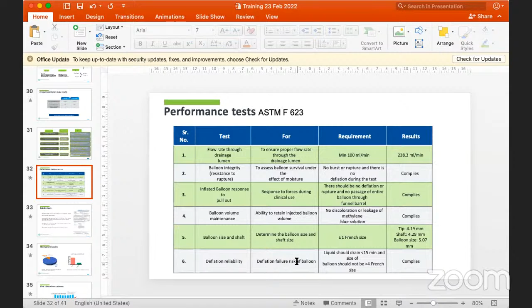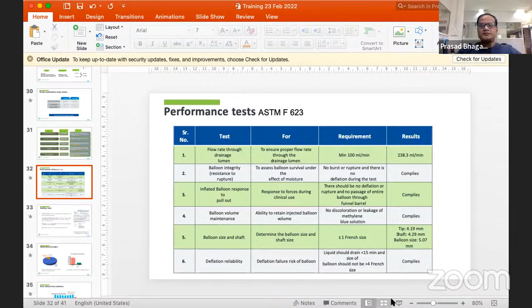This is used for the deflation failure risk of a balloon. Can you tell me what might be done in this deflation reliability test, or why it is important? Because we need to take out the distilled water we have inserted, sir. Yeah, you need to take out the distilled water, or you need to take out the catheter. Correct. The first thing was also correct, but the ultimate aim is to remove the catheter, and the balloon holds the catheter. Unless you deflate it, it is not going to get removed. So this sixth test is done, and our catheter also complies with this test.